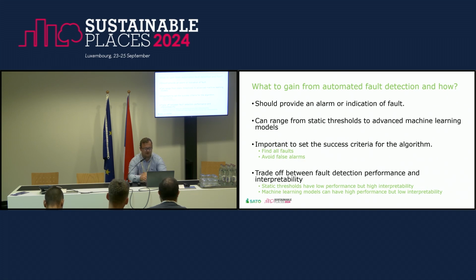But in order for these algorithms to succeed, there are basically opposing goals. Of course we would like to find all faults. That would be nice. The issue with trying to make an algorithm that does this is that we have a very high risk of adding too many false alarms, which has been found to decrease the trust in the system. So even if the system finds all faults, if it also adds a significant amount of false alarms, the operational personnel has a risk of simply not trusting the system and thereby ignoring the fault alarms.